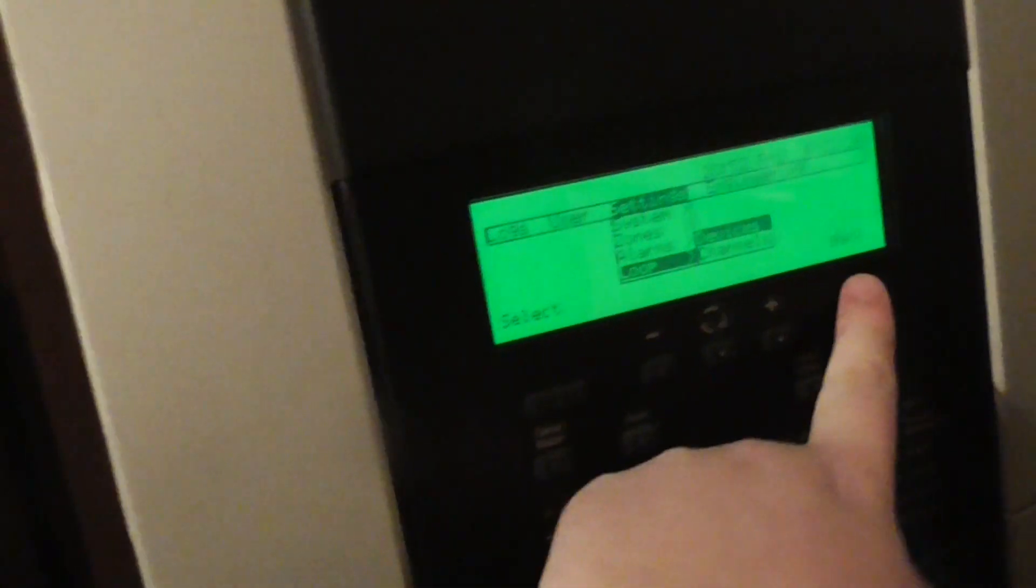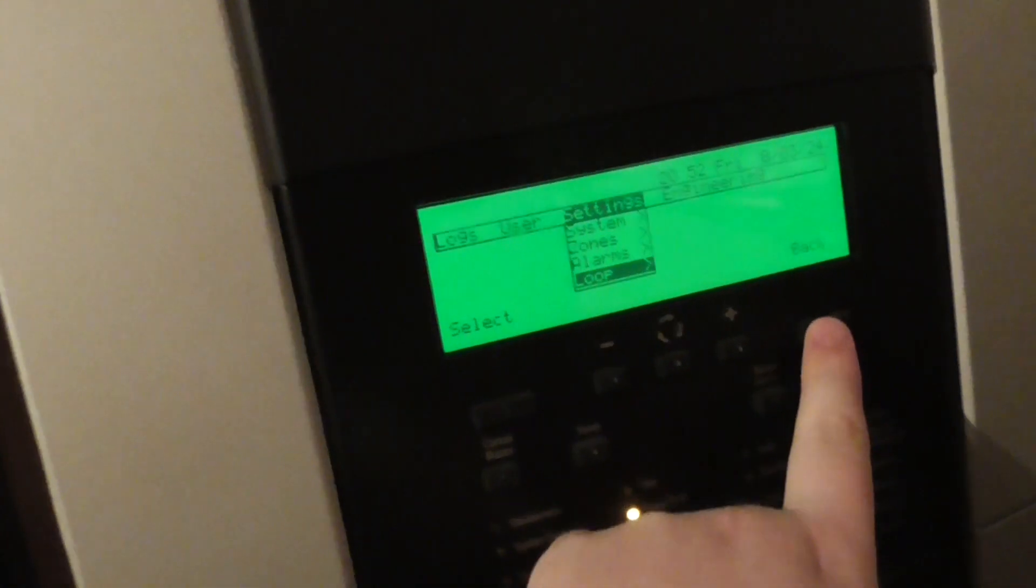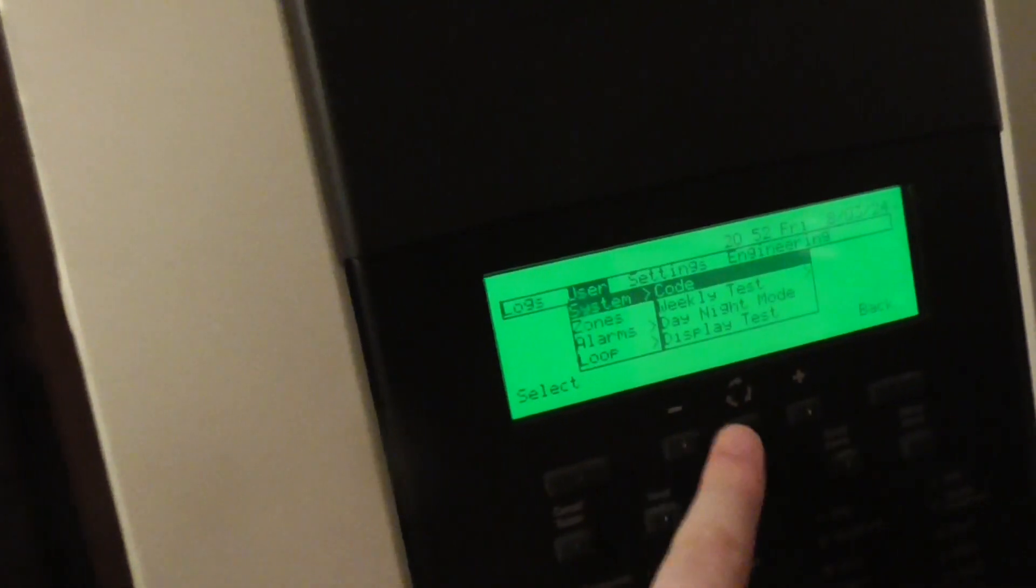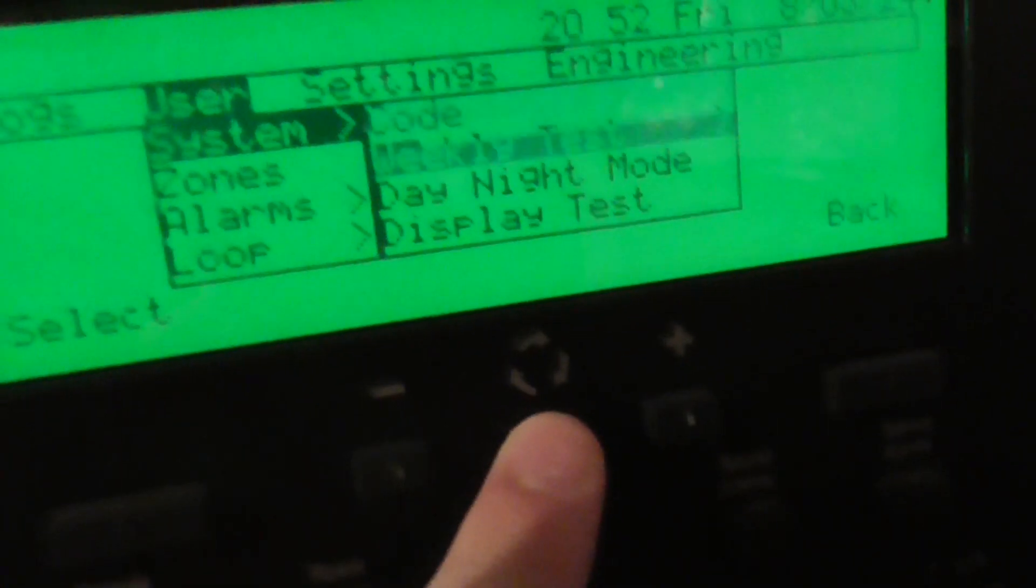Yeah, that's basically going to be it for this system test. I think to finish off the test we'll do a quick lamp test, a quick display test. There we go, I think the display test works. I'll show you guys the S-quads polling in the dark as well, so I'll turn the light off and show you guys the polling of the devices in the dark.